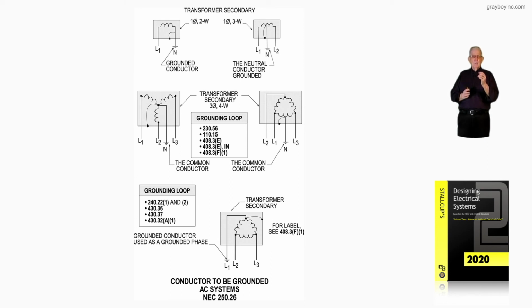Now your grounding loop starts 240.22, 1 and 2. 430.36, 430.37, and 430.32A1. Now those are loops involving a corner grounded system and high leg. So this kind of gives you the information that you need to know. Then at the bottom, notice there that we're actually grounding one of the ungrounded phase conductors. And that sometimes shakes up an electrician that's not used to this type of system.